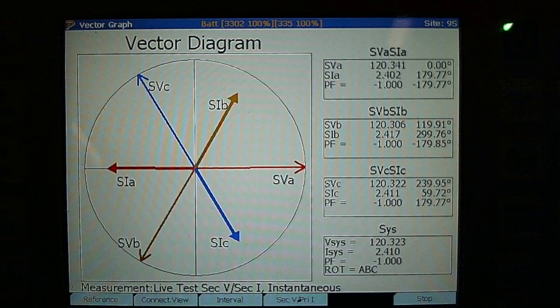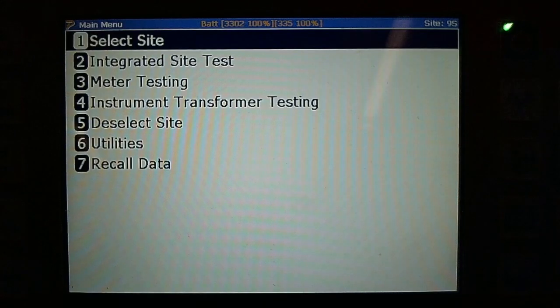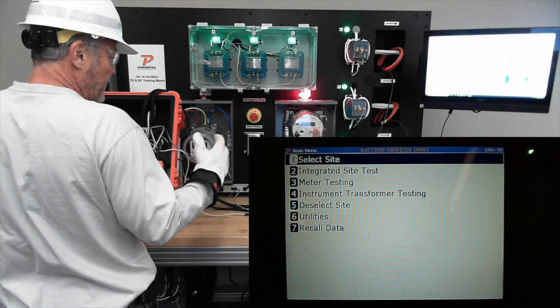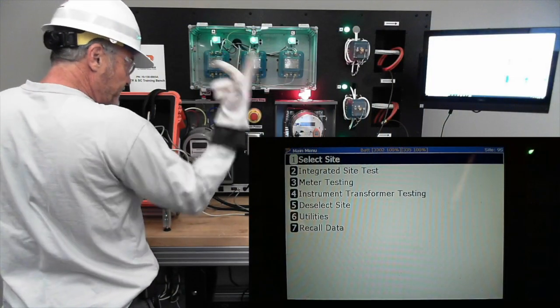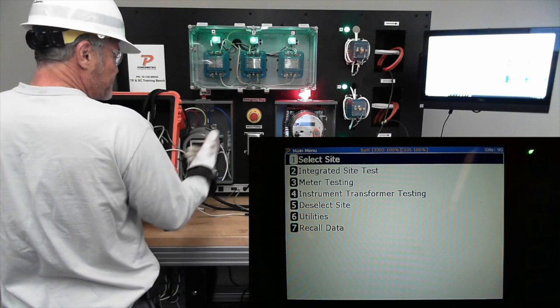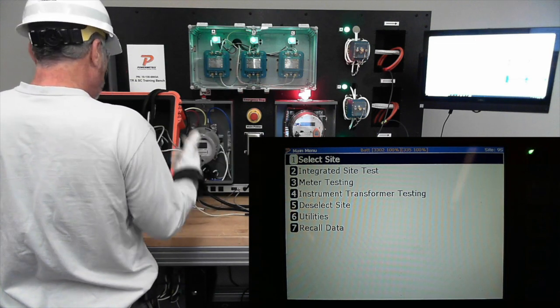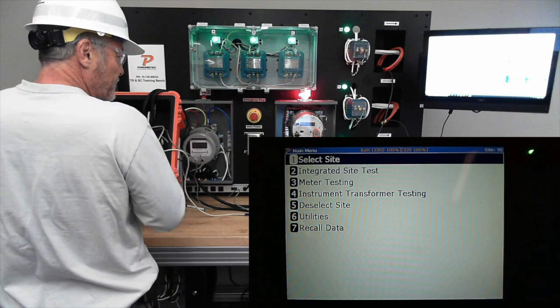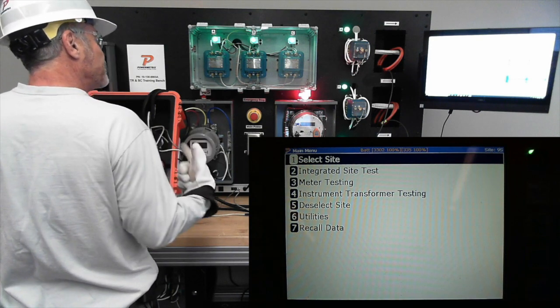So now I'm back out to my menu here, and I've chosen site 9S. The first thing I'm gonna do is run a customer load test. Before I start hitting the buttons, in the chat room - when I run a customer load test, which means I'm going to use the CTs and PTs if they're there, and everything connected to this meter right now, I'm going to measure and test this meter for registration - what would you expect to see on this?